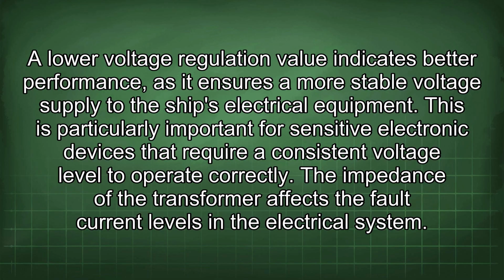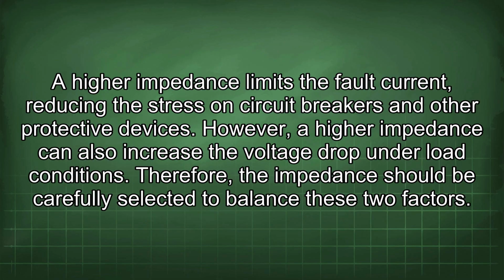The impedance of the transformer affects the fault current levels in the electrical system. A higher impedance limits the fault current, reducing the stress on circuit breakers and other protective devices. However, a higher impedance can also increase the voltage drop under load conditions. Therefore, the impedance should be carefully selected to balance these two factors.